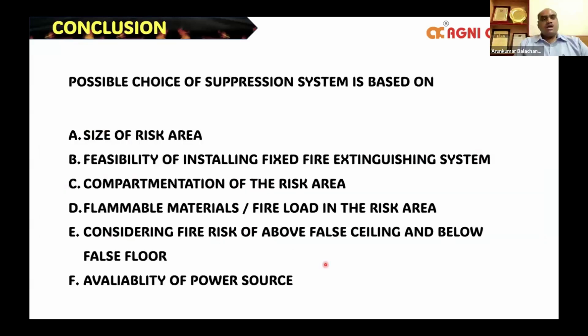So with that, we'll come to a conclusion of what type of suppression system we can possibly choose. The type of suppression system is based on the following minimum parameters: size of the risk area, feasibility of installing a fixed fire extinguishing system, compartmentalization of the risk area, flammable materials or fire load in the risk area, considering the fire risk of the above false ceiling and below false floor, and the availability of power source. Friends, just by preparing some bill of materials and asking for fire protection in a data center, it may not provide the desired protection that is required. We should always go in, design the best possible choice of detection and the best choice of suppression system based on the above criteria.